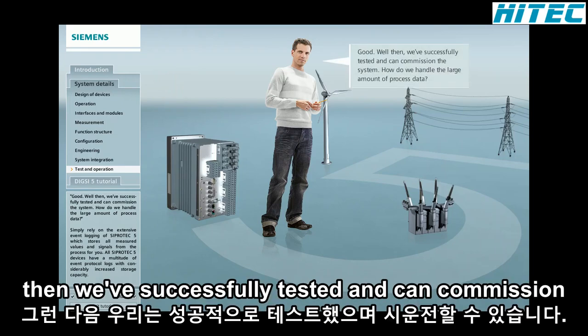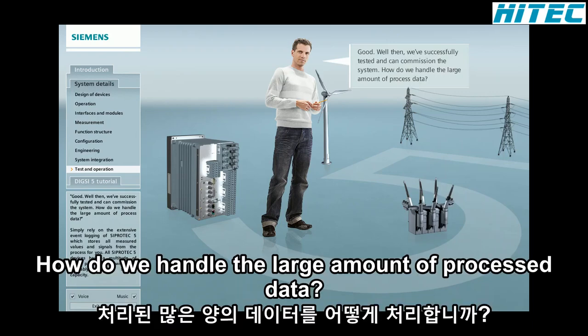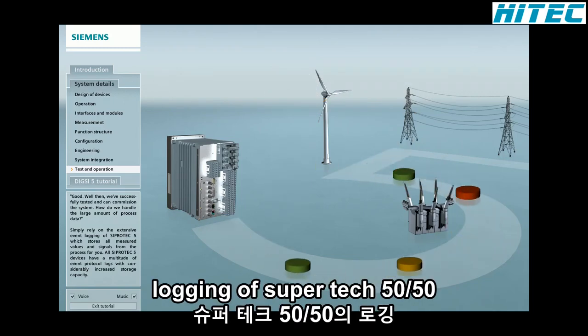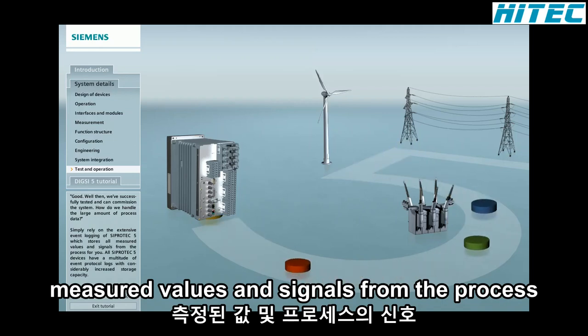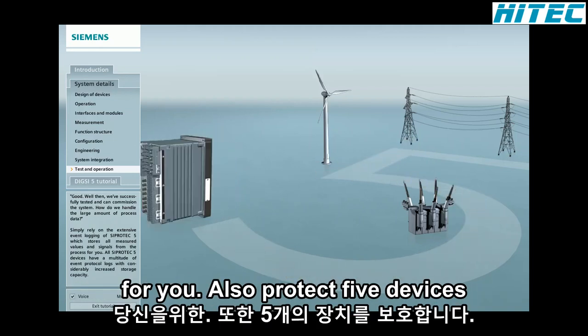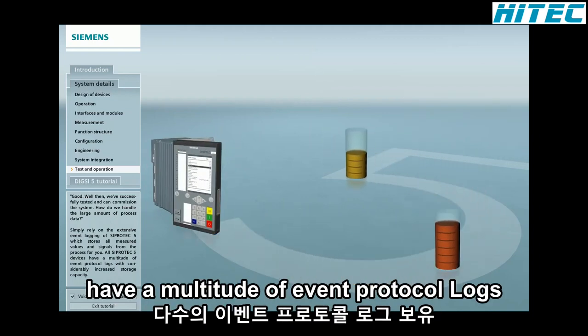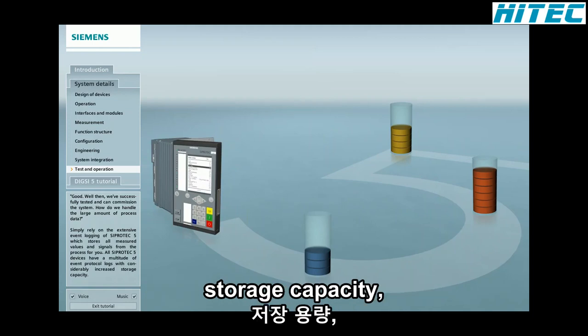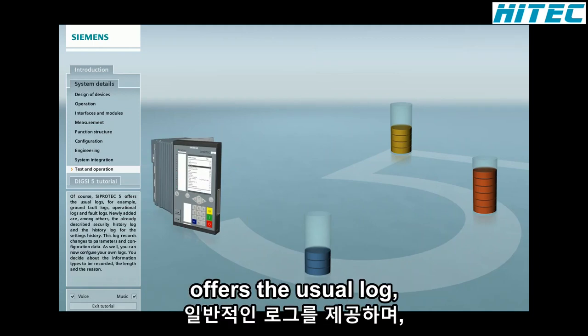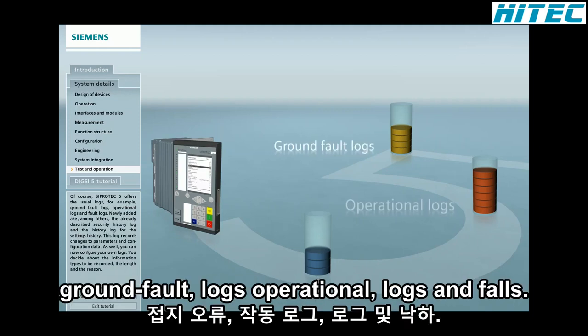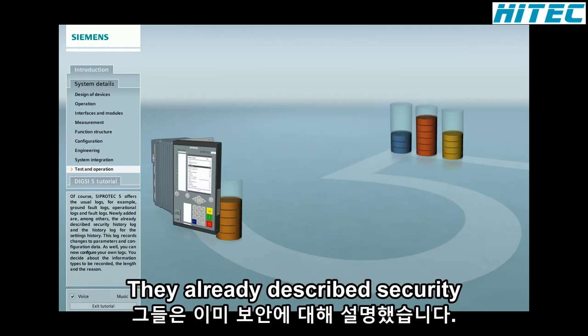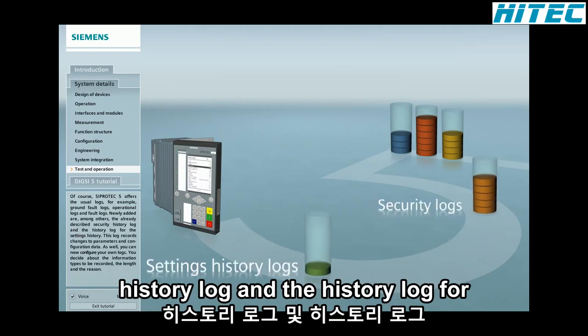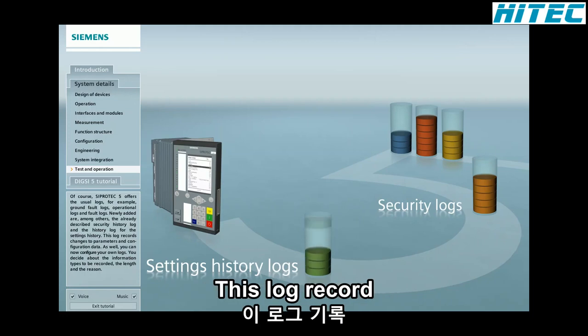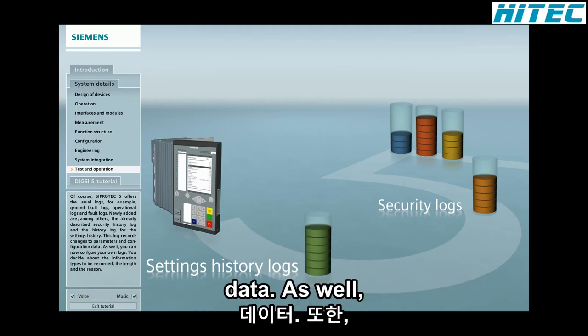Good. Well then, we've successfully tested and can commission the system. How do we handle the large amount of process data? Simply rely on the extensive event logging of SIPROTEC 5, which stores all measured values and signals from the process for you. All SIPROTEC 5 devices have a multitude of event protocol logs with considerably increased storage capacity. Of course, SIPROTEC 5 offers the usual logs, for example, ground fault logs, operational logs, and fault logs. Newly added are, among others, the already described security history log and the history log for the settings history. This log records changes to parameters and configuration data.